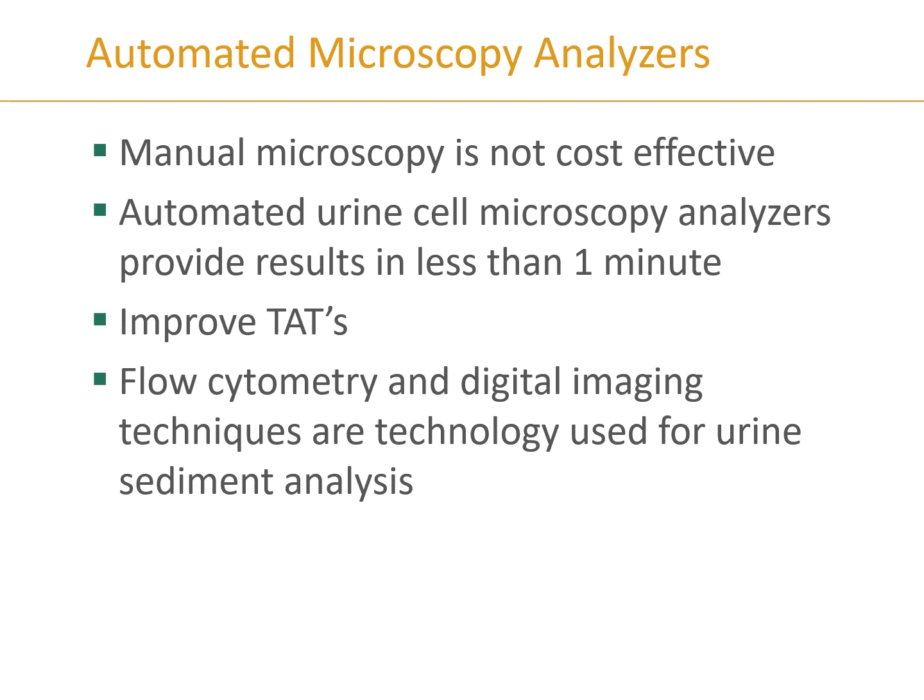Automated urine cell microscopy analyzers can provide results rapidly, usually within a minute or less. In contrast, manual microscopy requires spinning the sample, stopping other tasks, sitting at a microscope, loading the chamber or slide — at minimum a five-minute process. This improvement helps with turnaround time. These analyzers use flow cytometry and digital imaging to capture images of cells, compare them, and place them into proper categories.